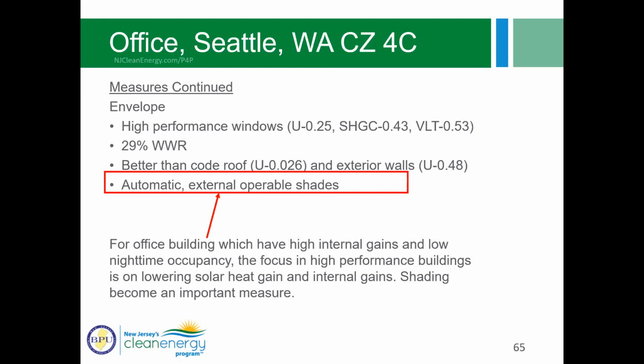Actually, in terms of building envelope, in some climate zones, because the internal gains are so high in an office, if you have an envelope with too high of an R value, you can actually hurt performance, because you could be trapping heat inside the building such that the building is warmer than outside, in an unwanted fashion. So you don't want to do that. So envelope, when I say envelope, like U values, things like that, is a little less important for an office building.